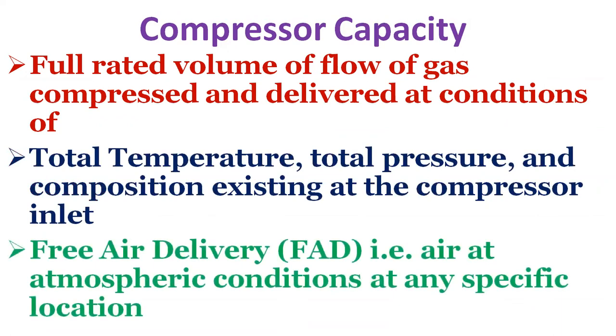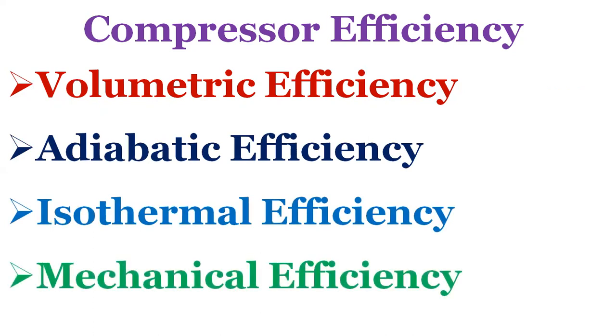The capacity of a compressor is the full rated volume flow of gas delivered at conditions of total temperature, total pressure, and composition at the compressor inlet — also called Free Air Delivery (FAD). Because altitude, barometric pressure, and temperature vary by location, FAD does not mean air under identical standard conditions. Several efficiency measures are used: volumetric efficiency, adiabatic efficiency, isothermal efficiency, and mechanical efficiency.